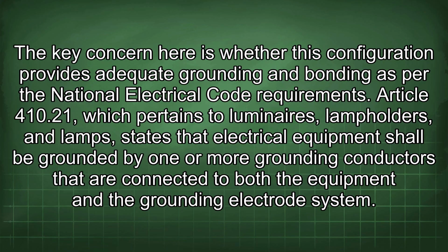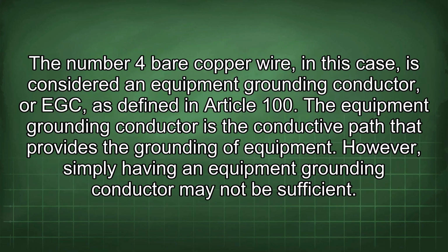Article 410.21, which pertains to luminaires, lamp holders, and lamps, states that electrical equipment shall be grounded by one or more grounding conductors that are connected to both the equipment and the grounding electrode system. The number 4 bare copper wire, in this case, is considered an equipment grounding conductor, or EGC, as defined in Article 100. The equipment grounding conductor is the conductive path that provides the grounding of equipment. However, simply having an equipment grounding conductor may not be sufficient.